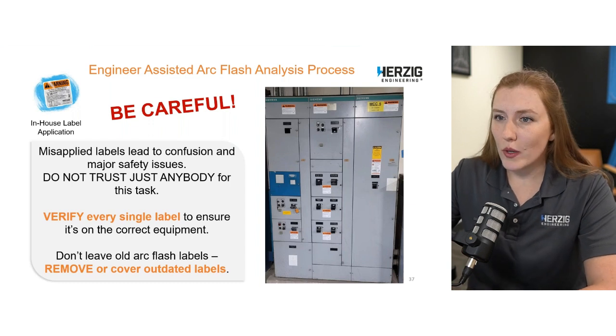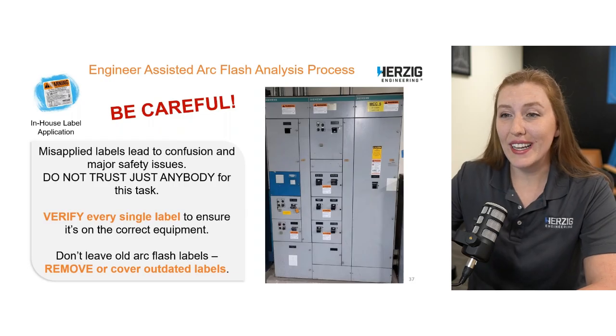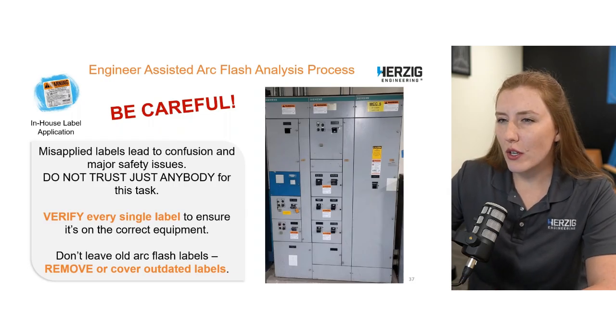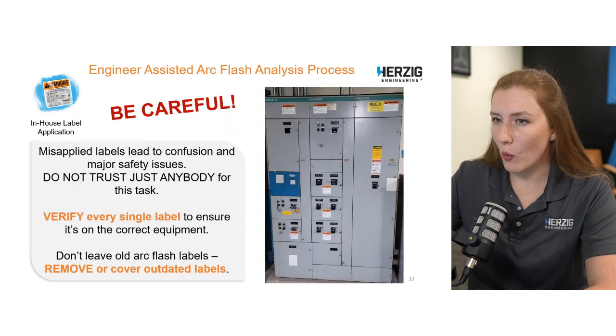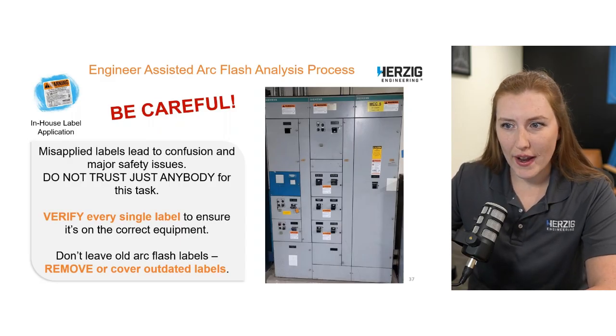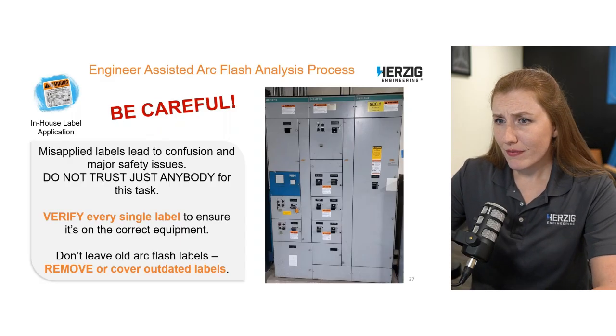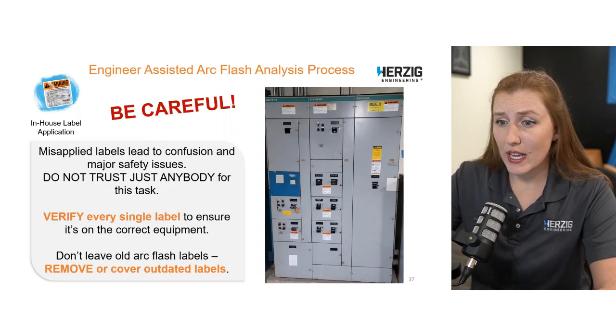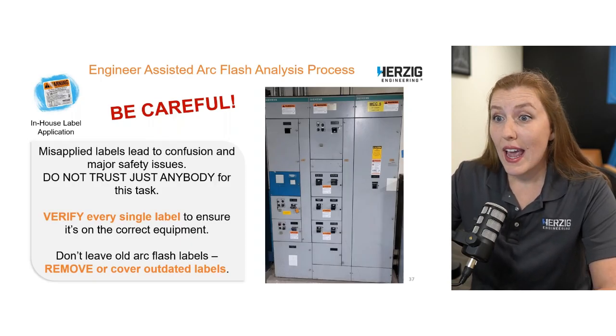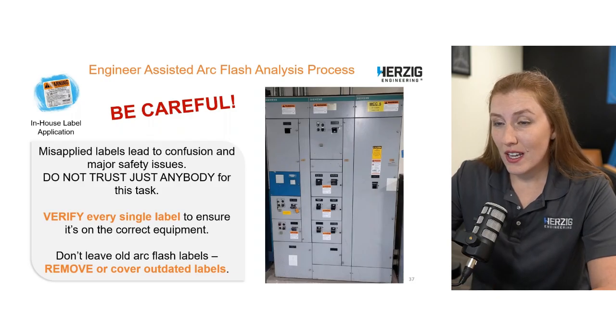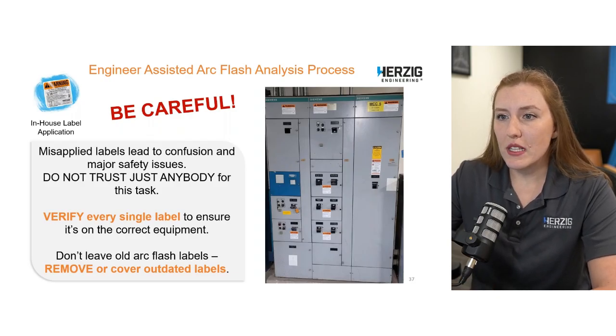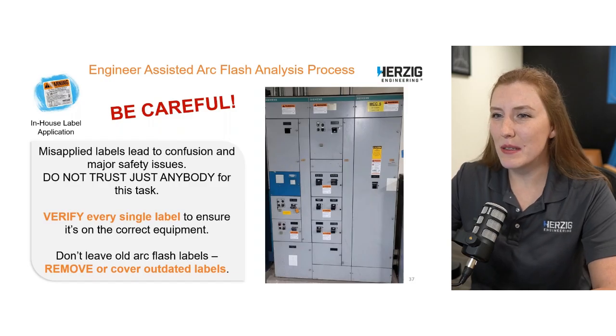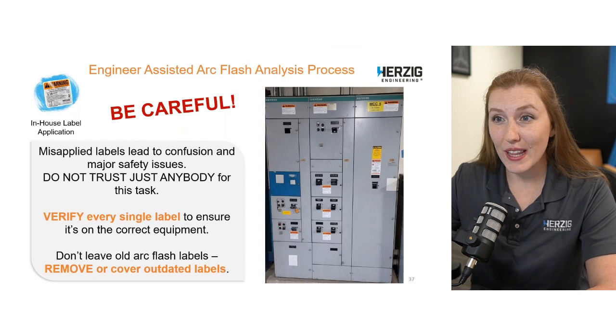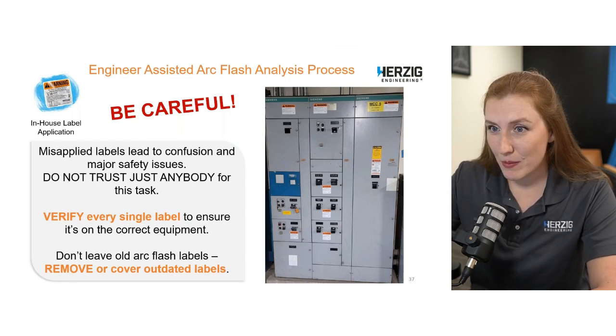I understand wanting to save costs and limit site time from an engineering consultant, I get that, but you have to be very careful that whoever is in-house doing that work knows what they're doing and why. Because right here we have, like I said, 3 different label types from 3 different rounds of studies, and they don't match. So if somebody walked up to this piece of equipment, they might be tempted to pick whichever label has the lowest hazard. And that is not the most up-to-date label. That is not the correct label.